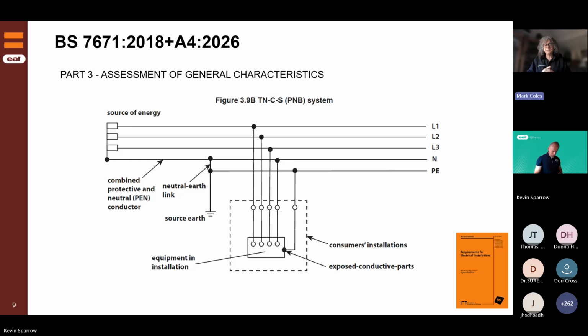Now there are two variants: PME, protective multiple earthing, and PNB, protective neutral bonding. PNB is the kind of thing you see in rural areas, out in a field, a farmhouse, with a transformer on a pole and a green and yellow conductor coming down to an earth electrode. From what I understand, the requirement from the DNO is that the earth electrode belongs to the supplier, but it's earthed as close to the premises as possible, and tends to feed just one building, one premises being the curtilage of the whole thing, farm buildings, whatever.